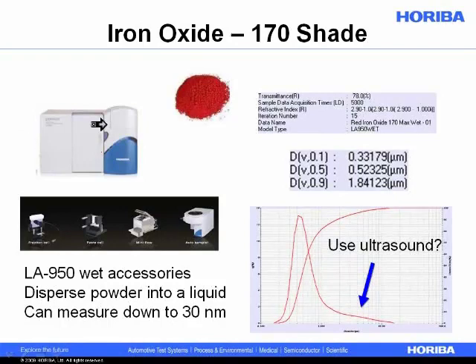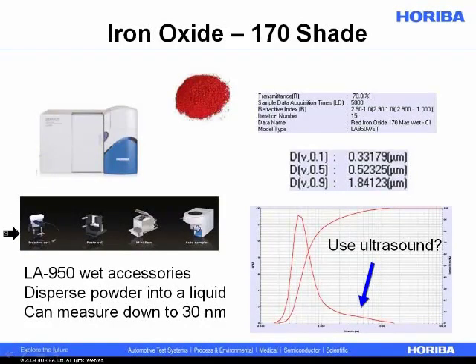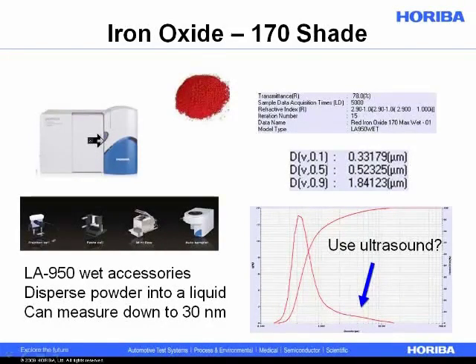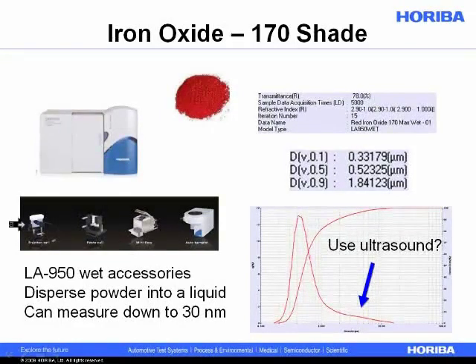Here is a wet reservoir — we simply recirculate the sample for the measurement. The LA-950 has several wet accessories, and for these samples, if dispersed in water, we just use the base system, which has a reservoir on the range of a liter. But we can use smaller volumes if we wish, for instance when we need to suspend the sample in a solvent and want to minimize solvent use.